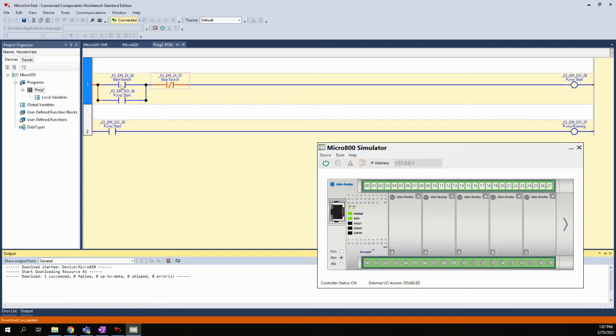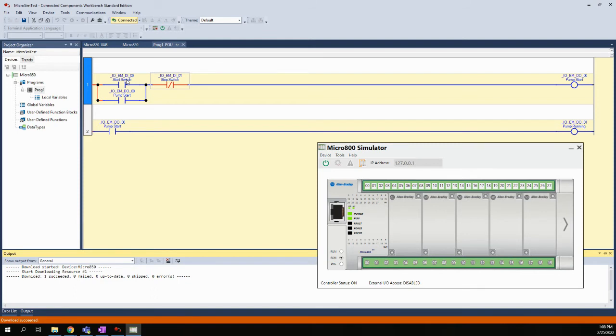Now the cool thing about the simulator is this is an actual input—the I/O EM DI 0-0 start switch. This is an output. So I can force the input on for testing. To do that, I can simply click on the input on the simulator.